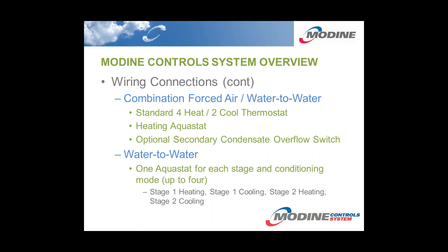Combination forced air and water-to-water systems are very similar. They use a standard four heat, two cool thermostat as well as a heating aquastat to control the hydronic tank. Water-to-water systems will use one aquastat or contact for each stage and conditioning mode, so you could potentially have up to four aquastats on the system.